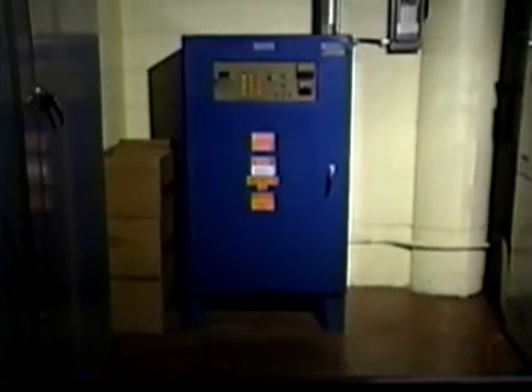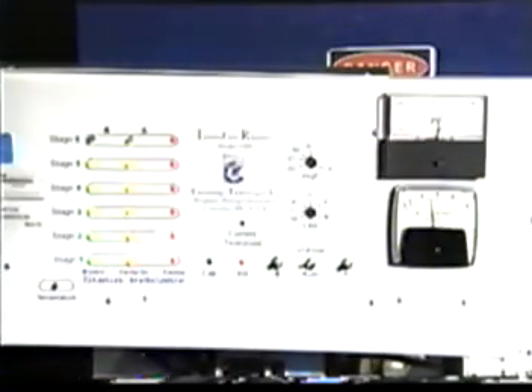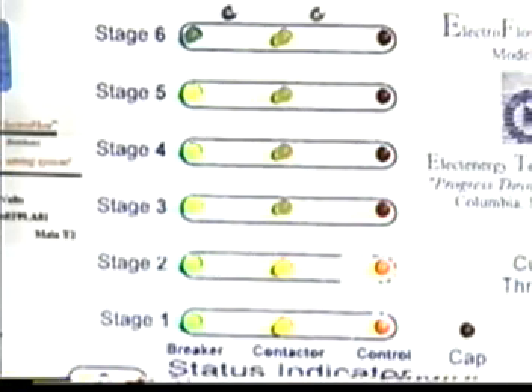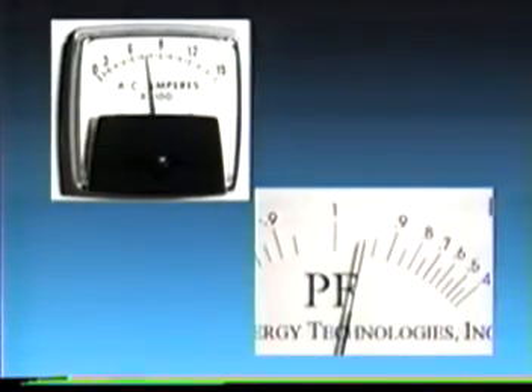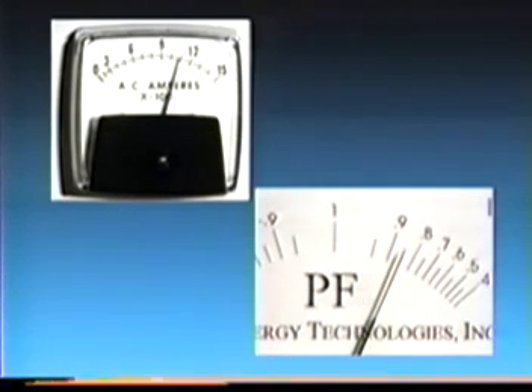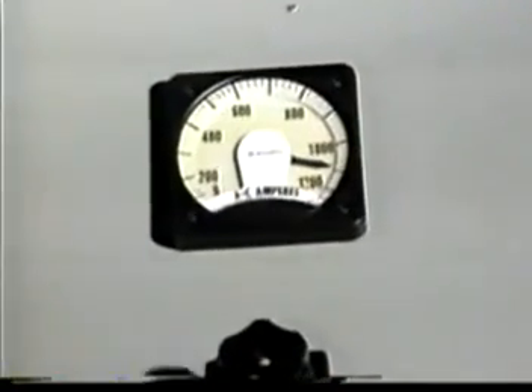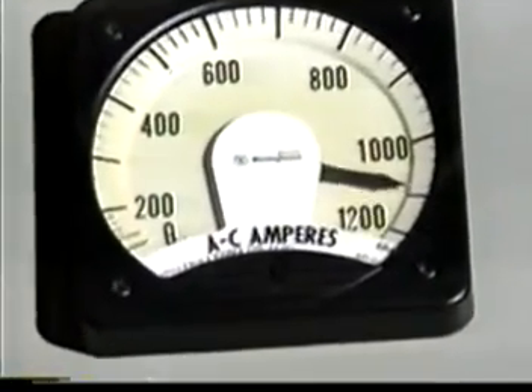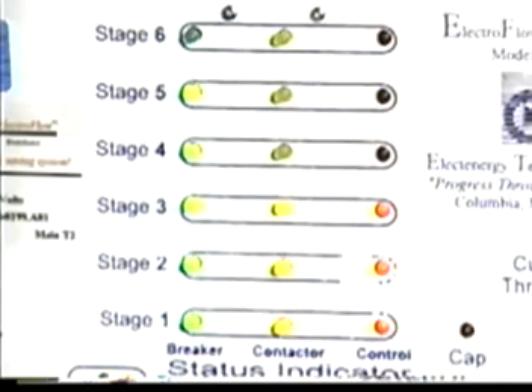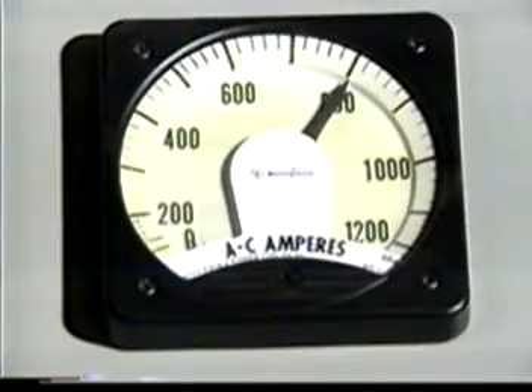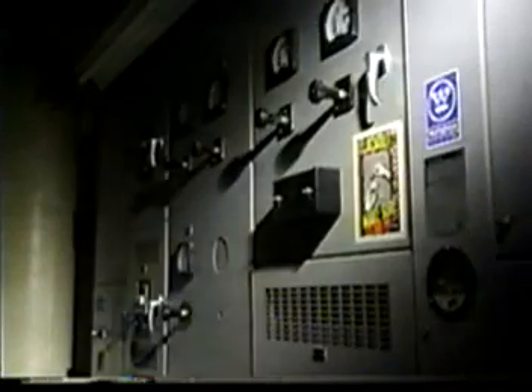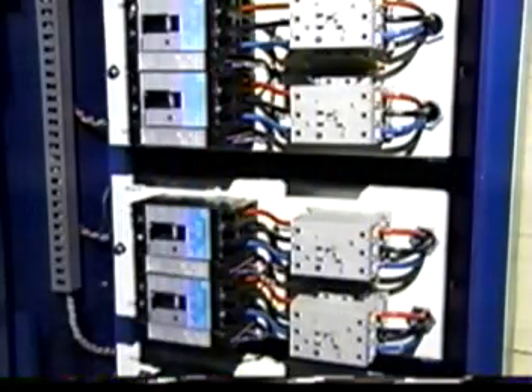What you are seeing is a K1-5 unit that is under normal plant load. As we stage down the unit, you can see the load in amps increasing and the power factor decreasing. Installation of the ElectroFlow units must be within 20 lineal feet of the distribution attachment point. 98% of the units are connected in parallel and can be installed in low, medium, and high voltage applications. As we stage the ElectroFlow unit back up, we can see the power factor improve and the amps decrease on the main transformer distribution. Each stage is protected, monitored, and activated as it is required or not required. If a failure was to occur in a stage, it would isolate itself offline and the rest of the system would continue to deliver its functions.